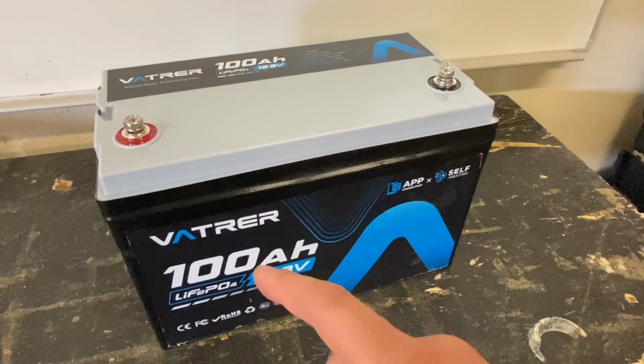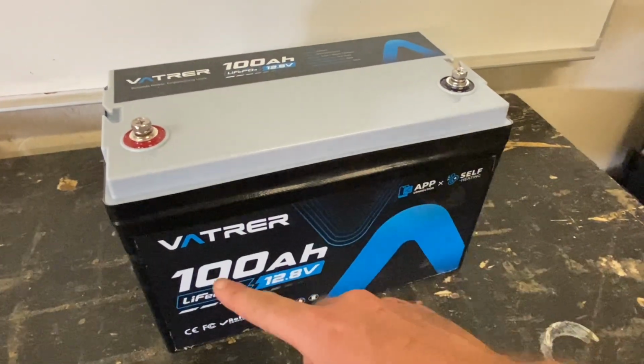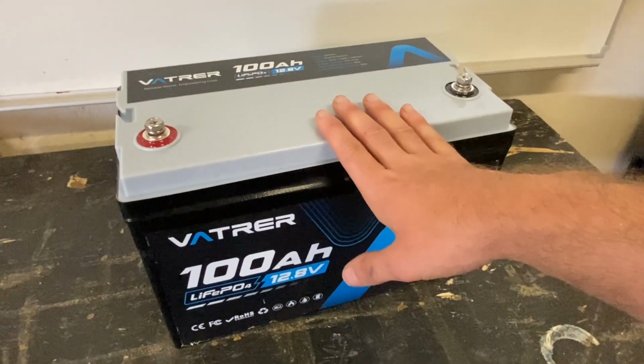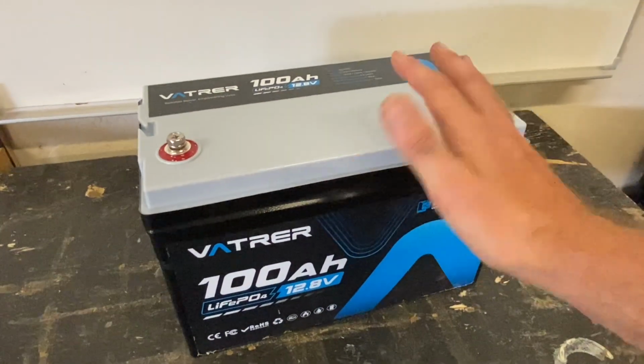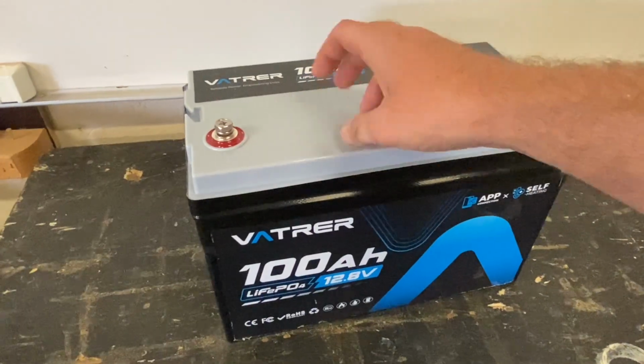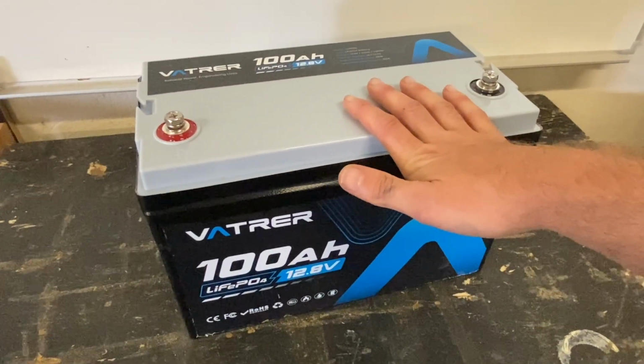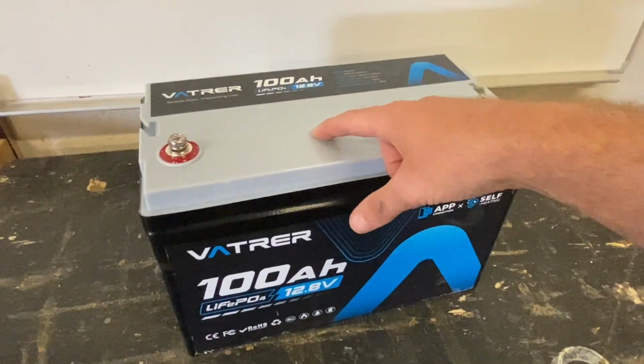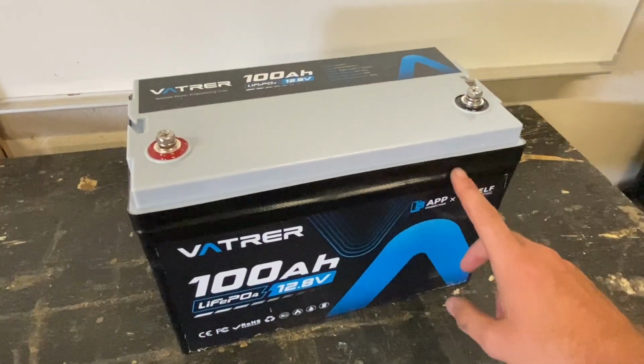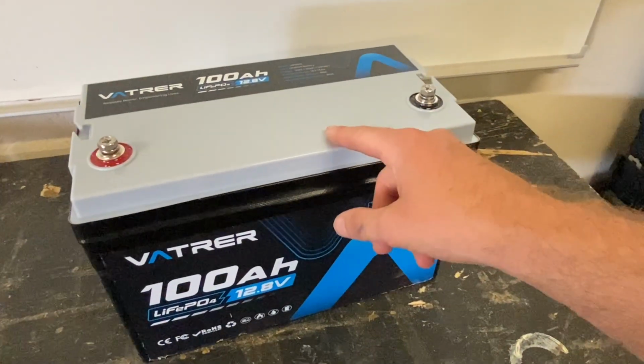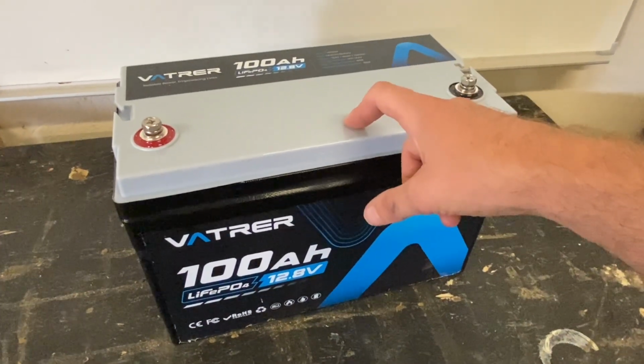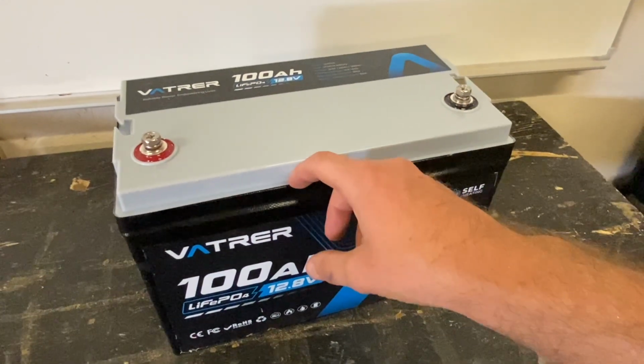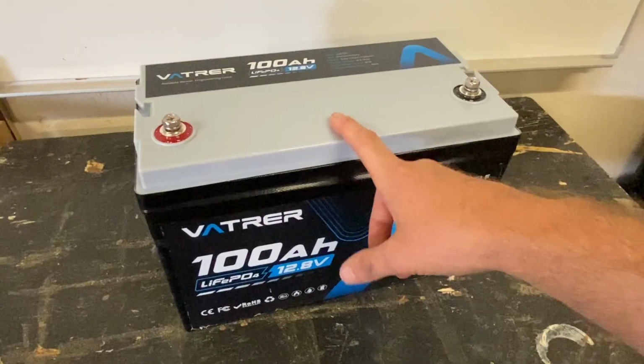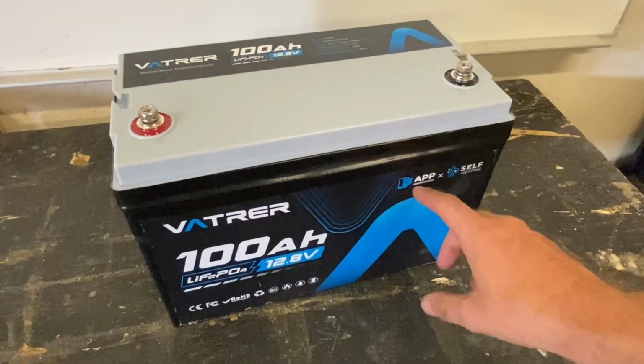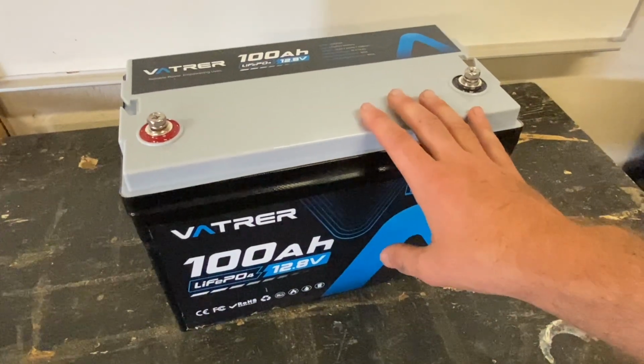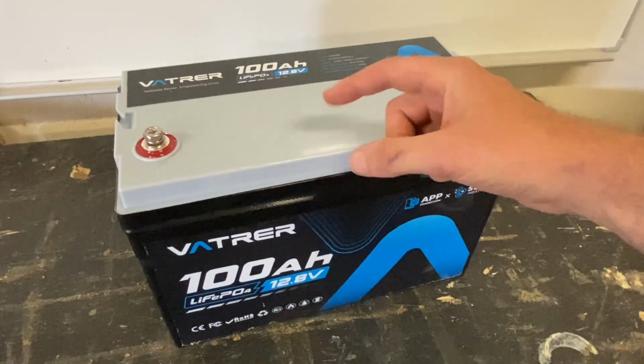So to recap, the 12.8 volt 100 amp hour lithium iron phosphate battery from VATRER is, in my opinion, a solid battery. The build quality is pretty much excellent. They've used bolts instead of welded terminals inside the battery, which makes it somewhat serviceable. The heating function is a nice touch. I would like it a lot better if they added low temp protection even when there's low current coming into the battery, to make sure we've got enough solar or a big enough charger to keep this thing running and the heater function working flawlessly.